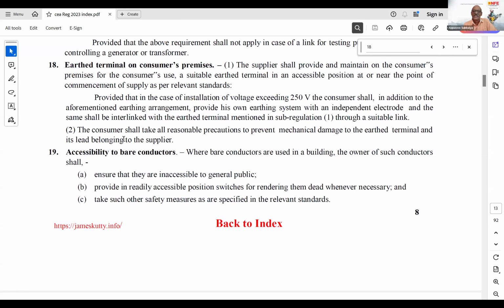Yes, this is the only thing that is yet to be corrected. Though this particular regulation has existed over a period of nearly 100 years, especially in our country, in the developed world and other countries there is no such issue. Because we have not clearly provided an integrated PME system, which is a protective multiple earthing system, by the distribution company up to the consumer premises. So if the consumer wants to connect as per regulation, he will be subjecting his person to a shock voltage. So the consumer should be aware of the earthing system of the distribution transformer, and then accordingly choose whether it should be connected or disconnected. He has to adopt a TT system. So Mr. Hemant Sali, I think you have raised the issue.